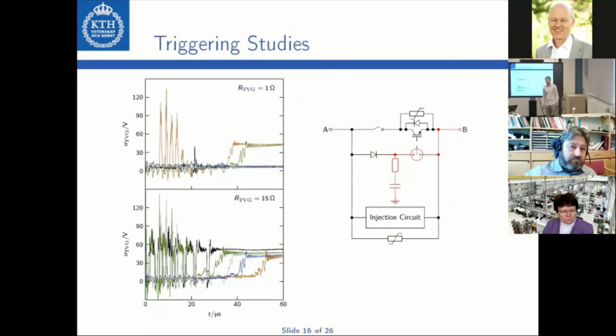We have conducted various experiments at low and high current levels, low and high voltages, and we found that the triggering process is very reliable, and actually we have never seen any mistriggering at all. The thing is that for this kind of operation of the triggered vacuum gap, low voltages are kind of a restriction because of the minimum voltage requirement, and the same goes for low current. Therefore, we have also put considerable effort into studying these kinds of current levels.